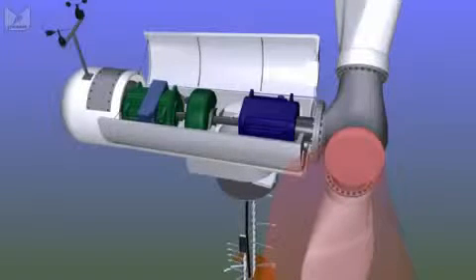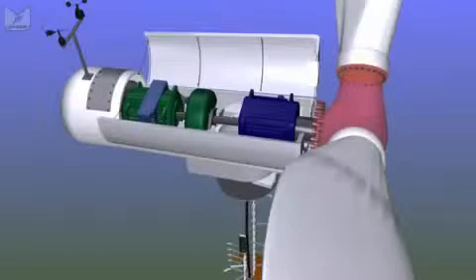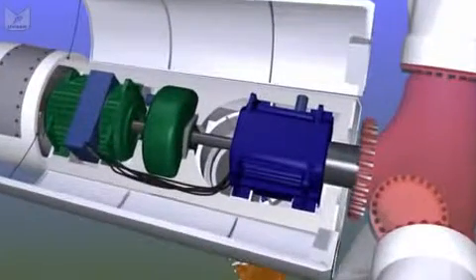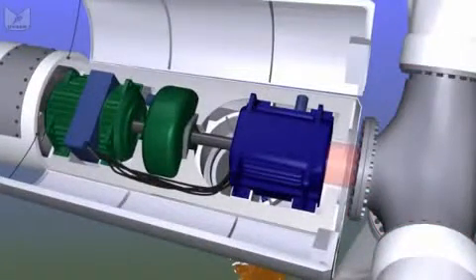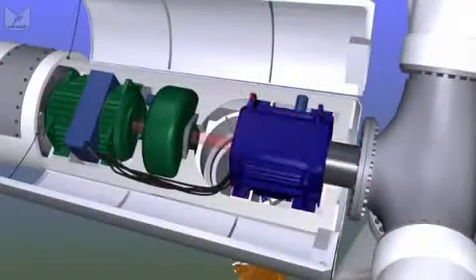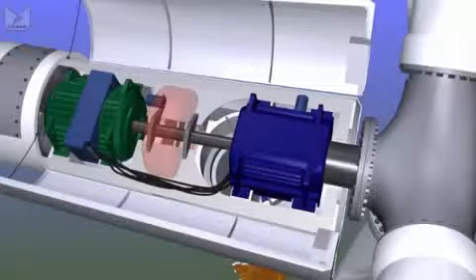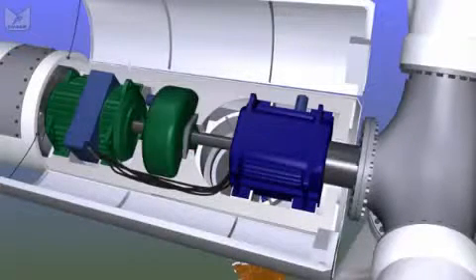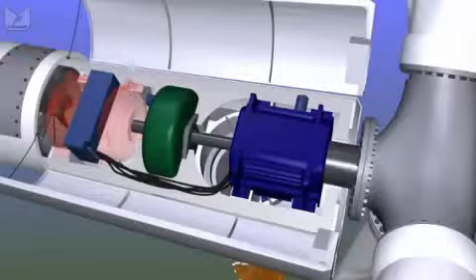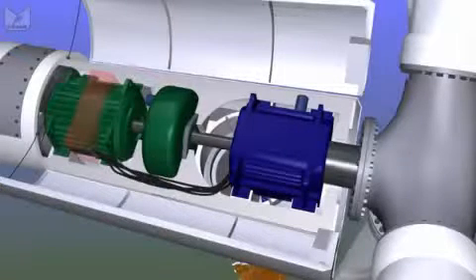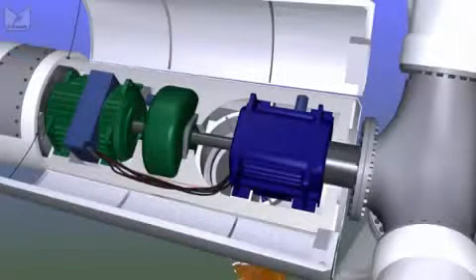And the blades can turn, or pitch, so that the angle they form with the wind can be varied. Out of the back of the hub, we have a shaft which leads into the gearbox, then a high-speed shaft, through a brake, into a generator. And that generator then supplies the electrical power at about 690 volts, all the way back down the tower to the base.